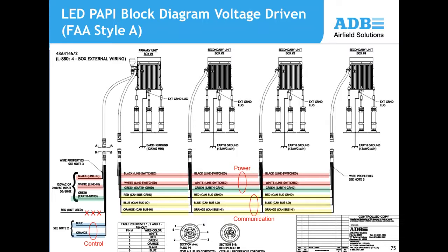Here is an example of mounting and installing the PAPI system. A typical four-box system shows that a voltage-driven PAPI has two conduits from the first box; the remaining units each have one flexible conduit carrying power and communication lines between the PAPI boxes. Power is shown in red and communication signal lines in yellow on the diagram.